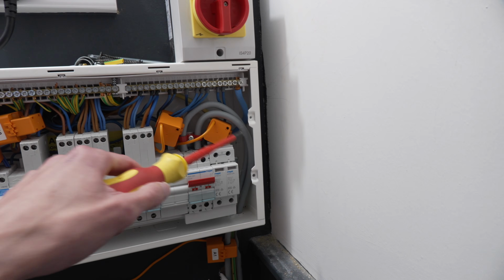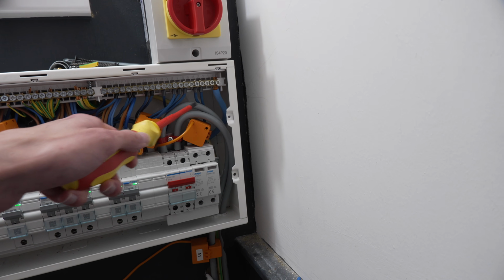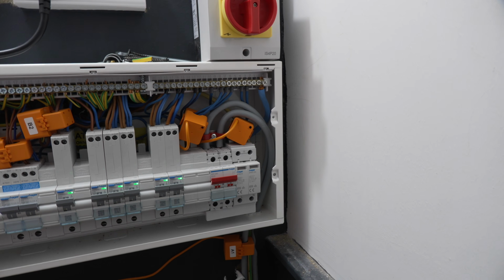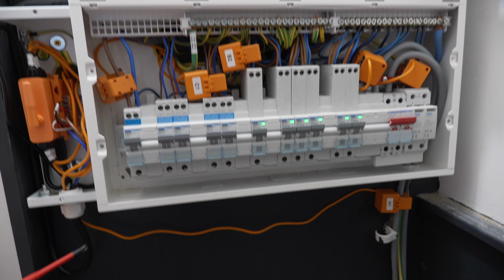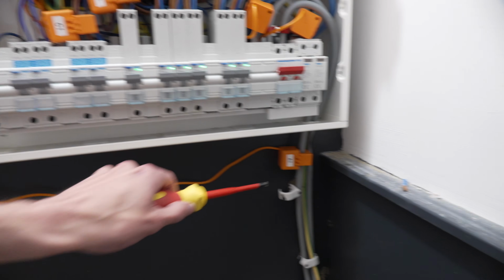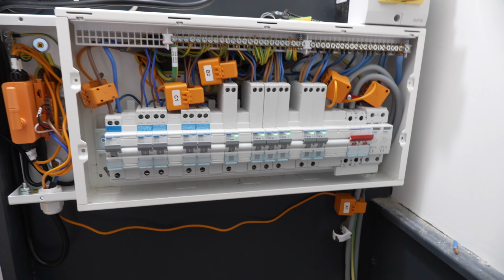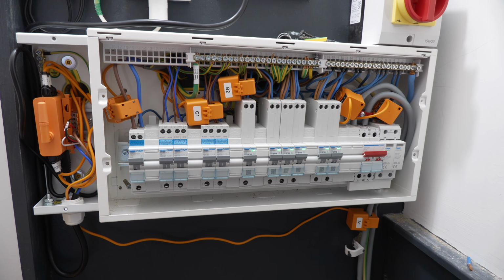So with these cables here, because they're bent round, if I try and clamp a CT onto this, because it's got a curve in it, it would potentially be too tight, and I'd crack the core. There was no point unnecessarily trying to shove more stuff in here, so bringing that meter CT out and connecting it externally was just so much easier, so that's what I've done there. But yep, that's all now installed.